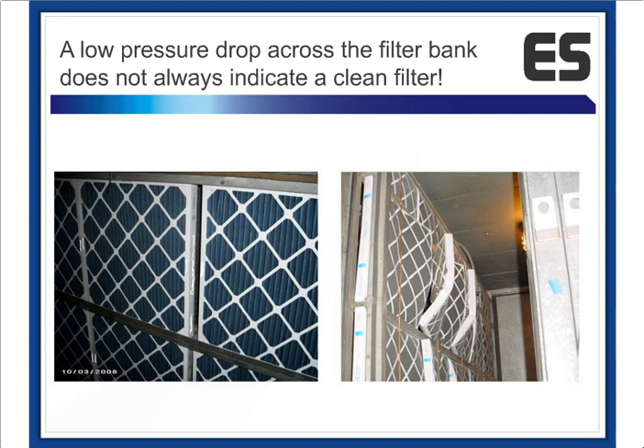On the right is an example of a filter that got too much debris loaded on it, so the air pressure started to buckle the filter, causing filter failure. In both conditions, the pressure drop would go to near zero because the air would bypass the filters.